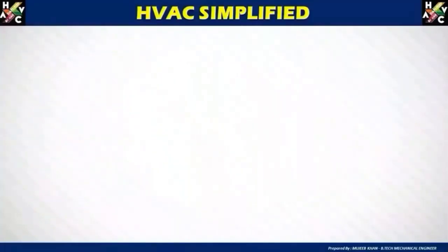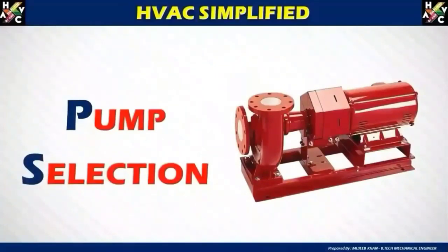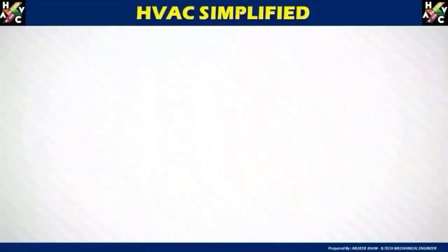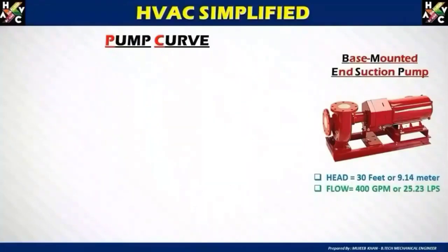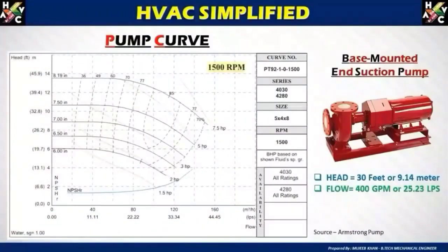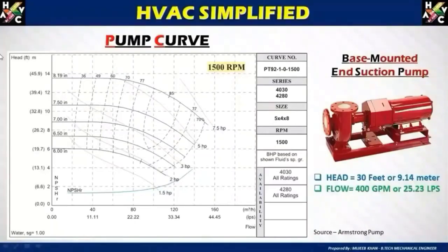Now let's see how to select the pump based on the pump curve provided by the pump manufacturer. For any pump selection, the manufacturer will provide a pump curve from which you select the pump. For our example of 30 feet head and 400 GPM — 30 feet equals 9.14 meters and 400 GPM equals 25.23 liters per second — here you can see a pump curve taken from Armstrong pumps. On the x-axis is GPM or flow in liters per second, and on the y-axis is the pump head in feet or meters.